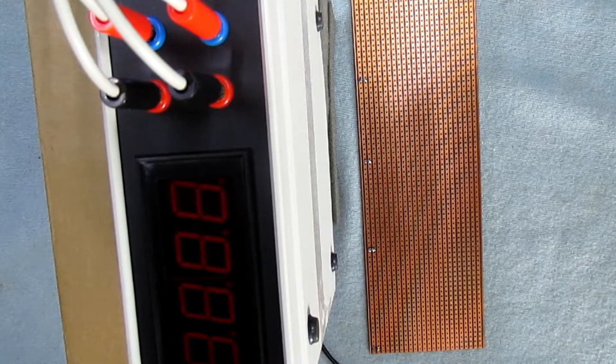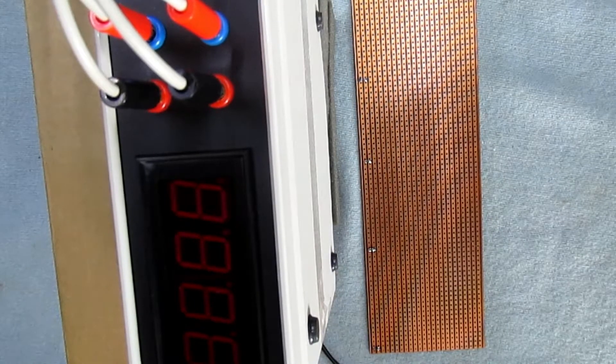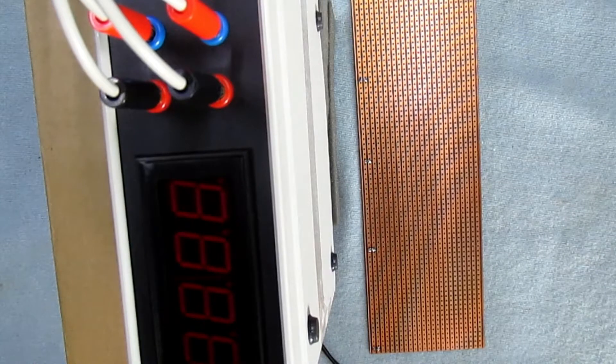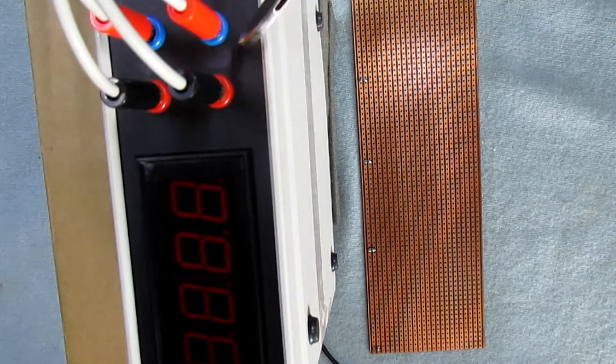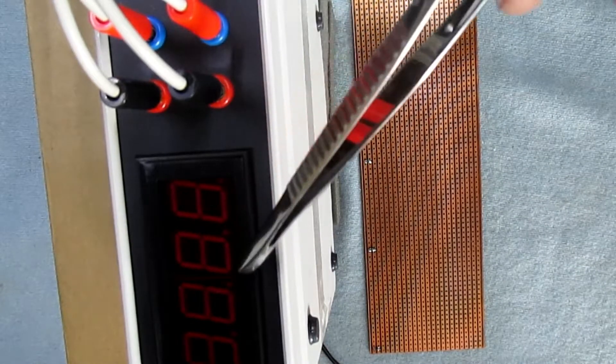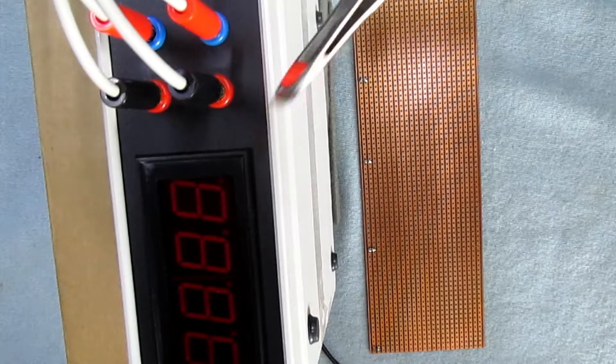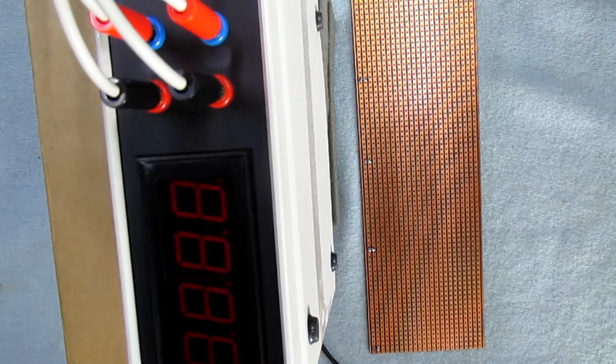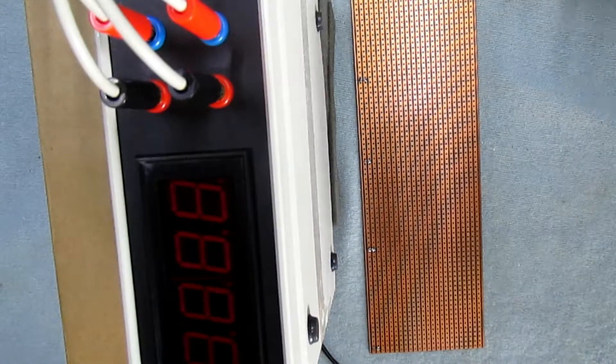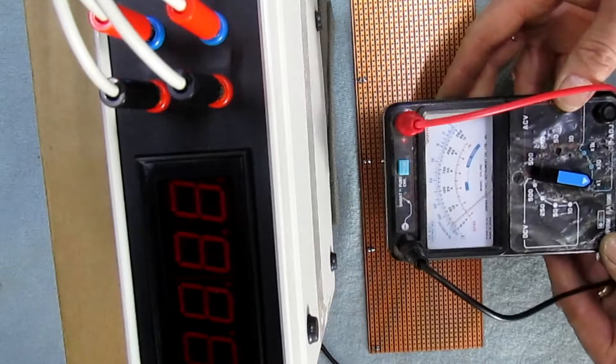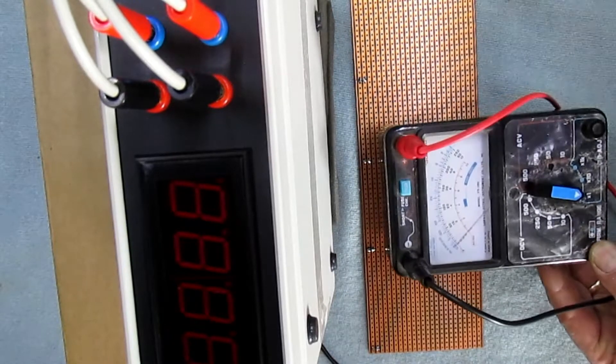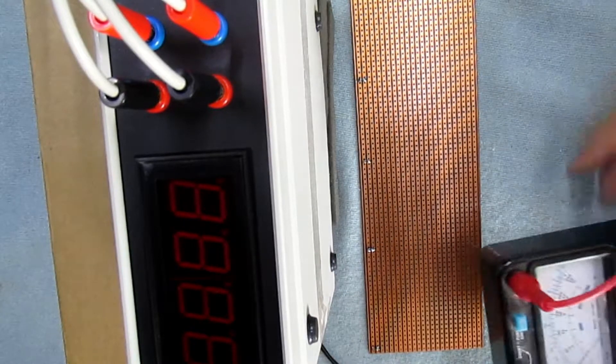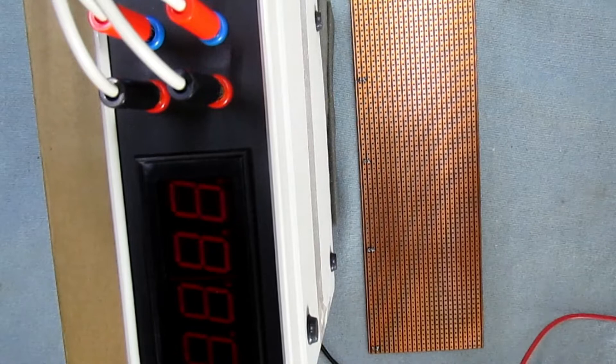Well, in this video I'm going to show you that's absolute load of rubbish. Now if you look here, there's a little instrument I made. It's a milli-ohm meter, it measures thousandths of an ohm, which is a lot lower resistance than your standard analogue or even your standard digital meter will read.